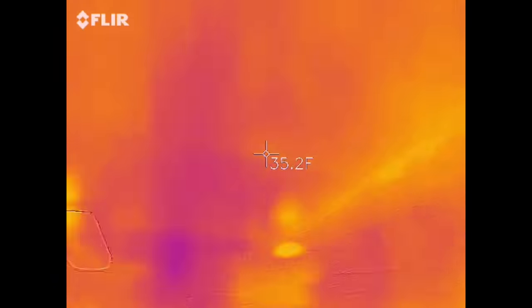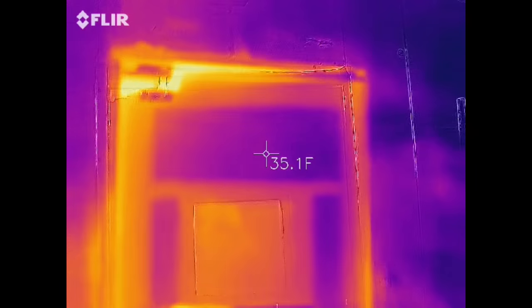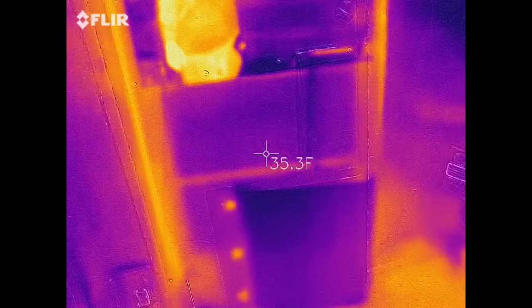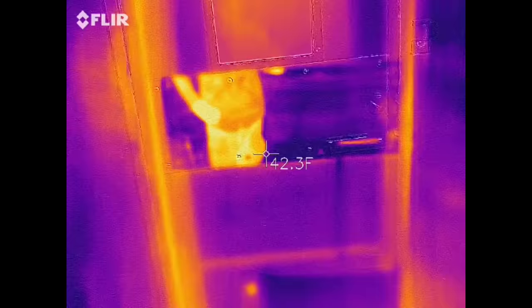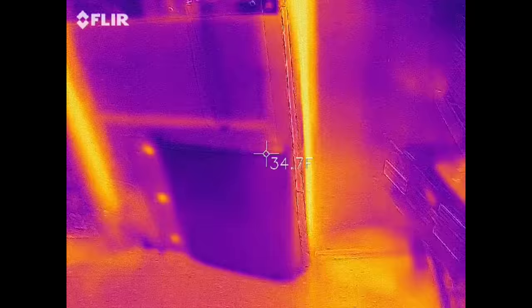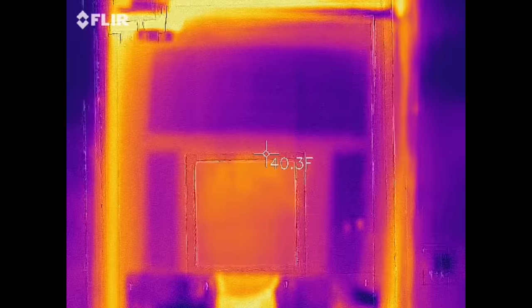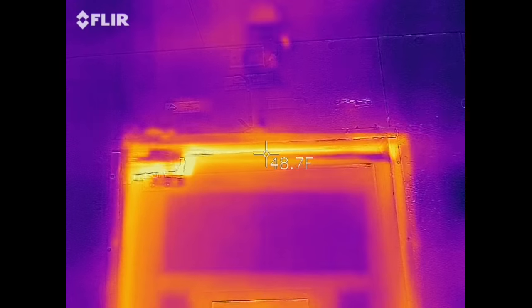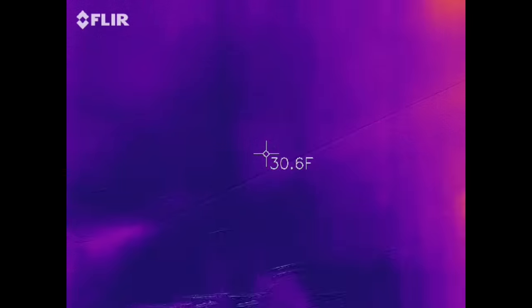Last and not least — you can see the infiltration around that door. There's really not a whole lot of insulating value to the door anymore. You can even see my reflection off the stainless, but yeah, you can just see the heat coming in. Even when that door is shut all the way, look at the heat infiltration from the top where it's not sealing. Definitely a problem.